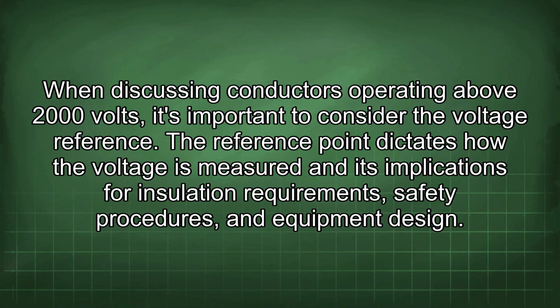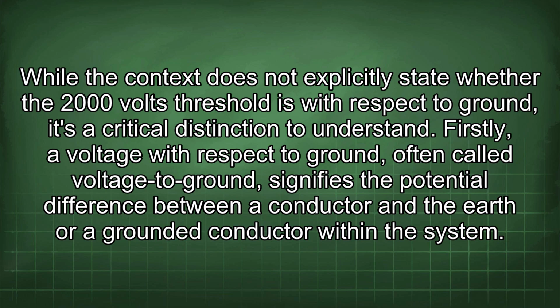When discussing conductors operating above 2000 volts, it's important to consider the voltage reference. The reference point dictates how the voltage is measured and its implications for insulation requirements, safety procedures, and equipment design. While the context does not explicitly state whether the 2000 volts threshold is with respect to ground, it's a critical distinction to understand. Firstly, a voltage with respect to ground, often called voltage to ground, signifies the potential difference between a conductor and the earth or a grounded conductor within the system.